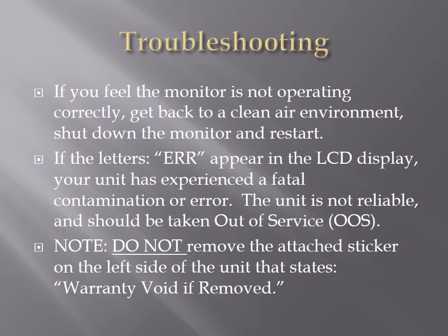All right, troubleshooting. Let's say you're at the station, or you're actually on scene of an incident, and you feel like this monitor is not operating correctly. This is what we recommend you do. First, get back to an environment that is safe, what we call clean or clear. Shut down the monitor by turning it off with the on-off toggle switch on the right-hand side of the unit. Wait about 10 to 15 seconds, and turn the unit back on and restart it.